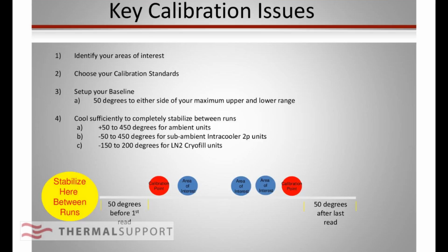And below that, you're talking about using organics, which are high purity organics that work great, but they take a lot more handling expertise. So we understand that's an issue, but best baseline you can, to your best ability, try to bracket your sample. And then between runs, try to cool sufficiently to be really stabilized. If you're doing an ambient run, if you get down to 50 and the control light's on, everything's working fine, that's great. If you're doing a subambient Intracooler, once you get down to about -50, you're doing pretty good. It's always nice to go down to -65, but below -50 you're getting pretty stable. And then LN2 getting down to about -150, you're pretty stable.